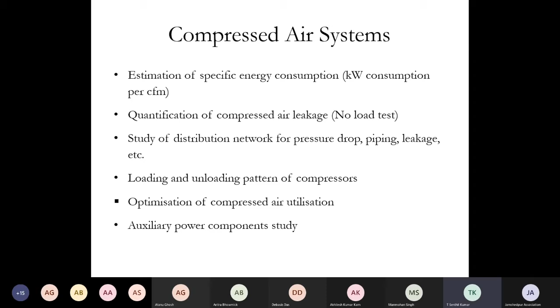Compressed air systems are also one of the major energy guzzlers in a system. A good amount of energy saving opportunity is possible by studying the performance and comparing it with the design specification. Invariably, all industries will have some leakage, which is inevitable. Certain amounts of leakage are permissible, and we can carry out a leak test to quantify the leakage, and find ways to plug it and save energy in the compressed air system.